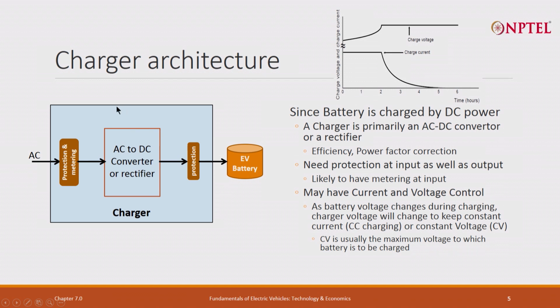It may have voltage and current control, because the battery may require a different DC voltage at different times. When it is empty, it may require one volt; when it is full, it requires a different volt. So you may have to change the voltage, and almost always you change what is called current. So you charge using two modes, what is called constant current. You see here, in the beginning you always charge using constant current.